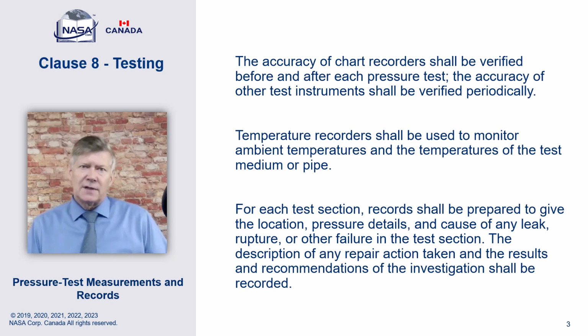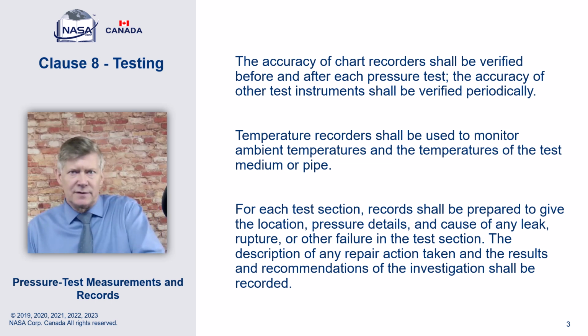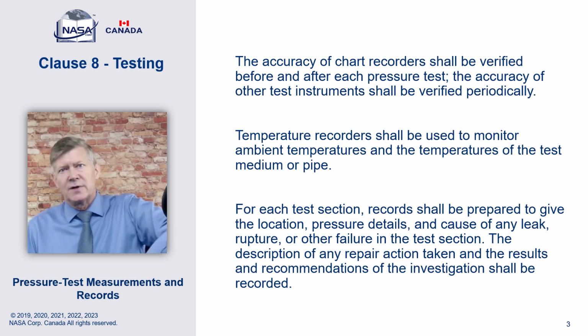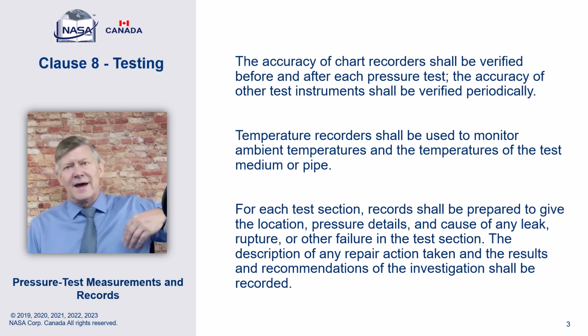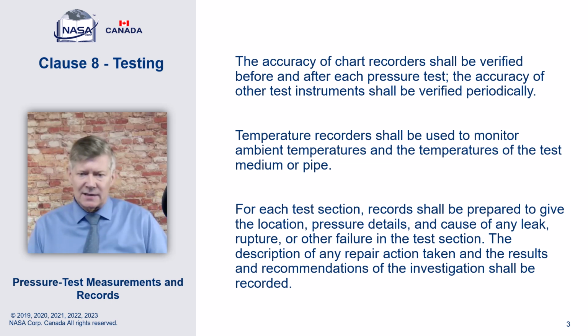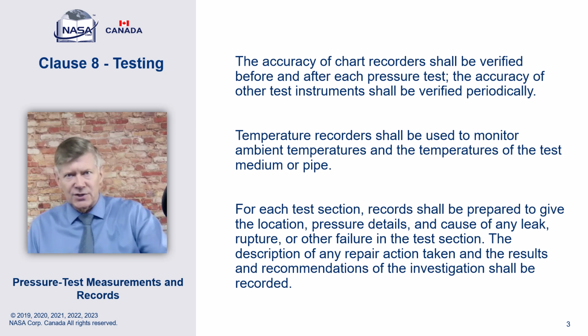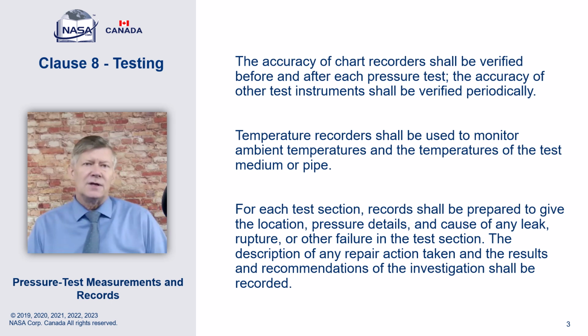Okay, now typically when we use calibrated instruments and they're found out of calibration at the next calibration cycle, okay, we have to look at where was that instrument used, right, where that deviation would have an impact on the results. So let's just say hypothetically, I send my gauge in for calibration, it comes back, it's calibrated, and I use it for a year, okay, and in that year I do 12 tests. Okay, at the end of the year, I send it in for calibration. They send it back with a report that says they received it 10% out.